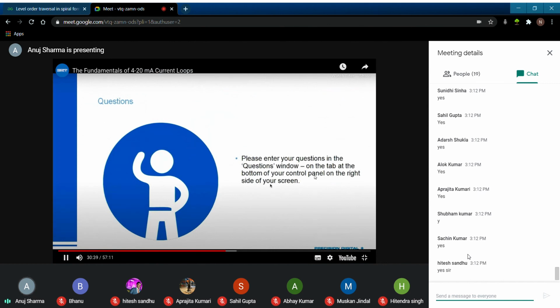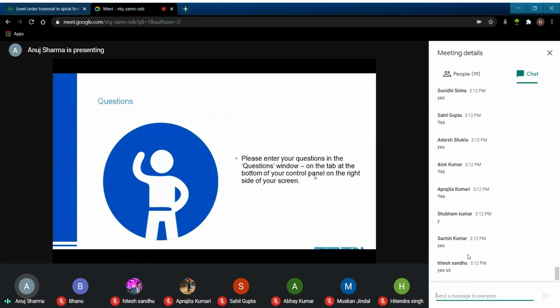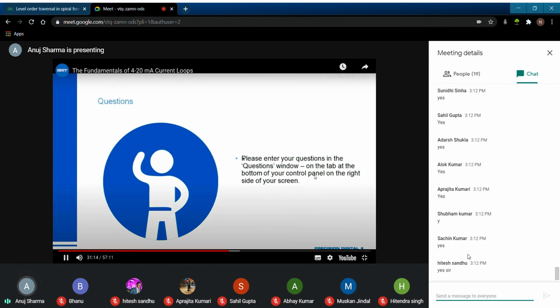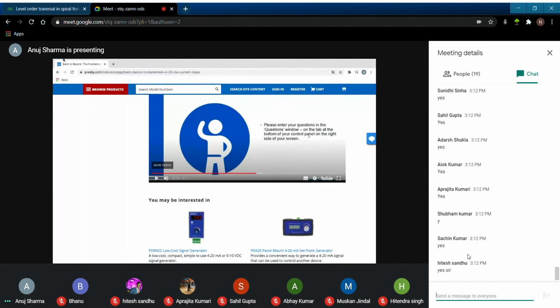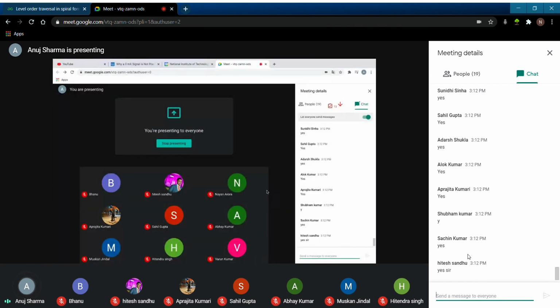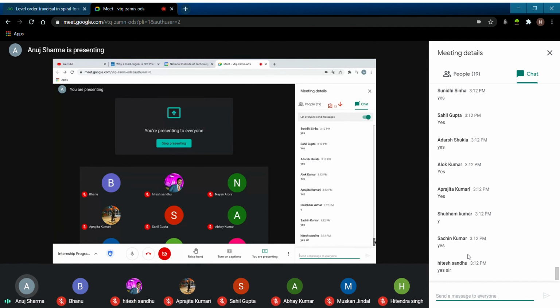Only really going to be varying by about half a milliamp. When you have the entire range you're trying to display or control in half a milliamp and not the full 16 milliamp range, then you become susceptible to additional noise effects. You also run the risk that minor fluctuations in the transmitter's ability to control the current, or inaccuracies happening while the flow is being measured, are going to be much more pronounced. So the lesson is you want to use as much of the full 16 milliamp range, the 4 to 20 range of your transmitter, as you can. That means either selecting a transmitter. Now Mr. Ryan has told us one more important thing, and that is, can someone answer what he has said, that you need to use your full range.